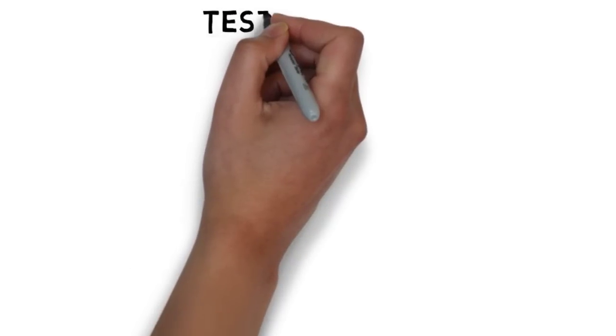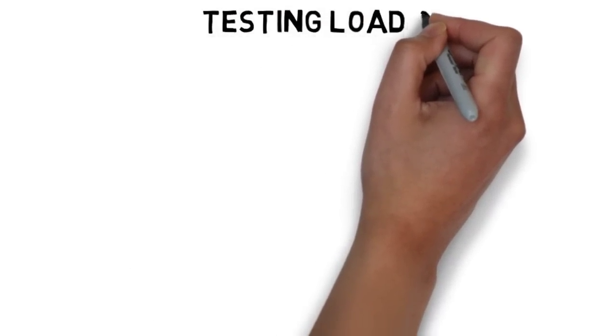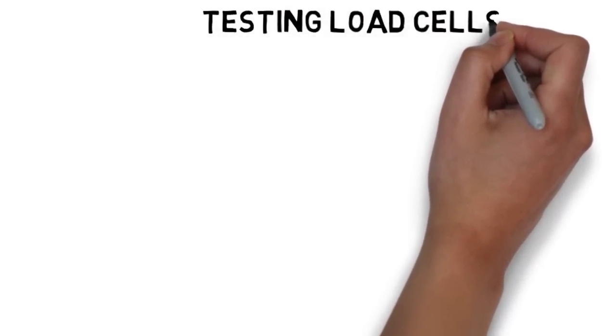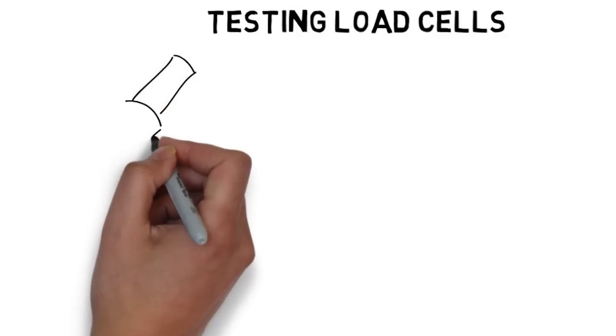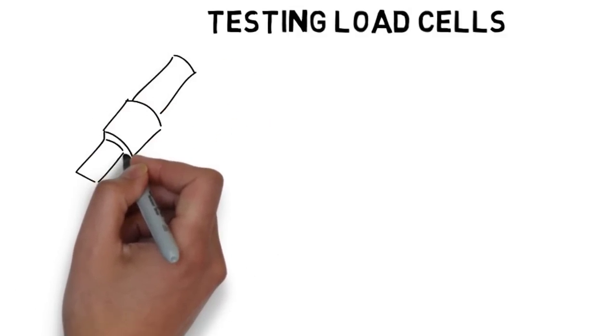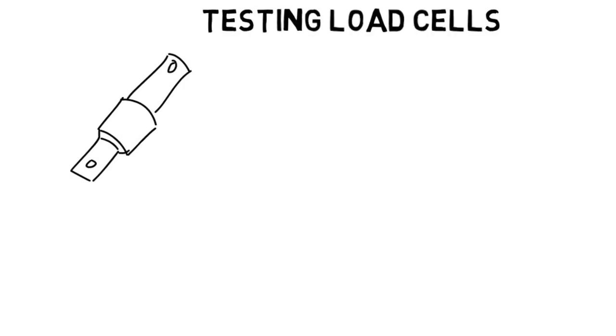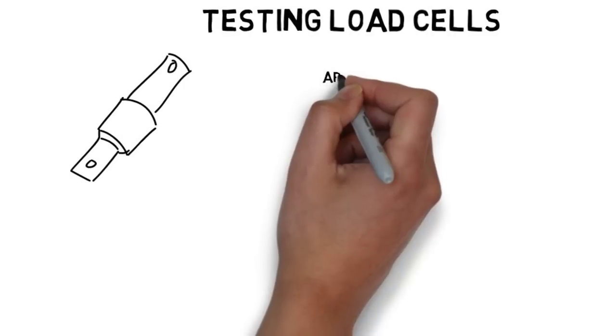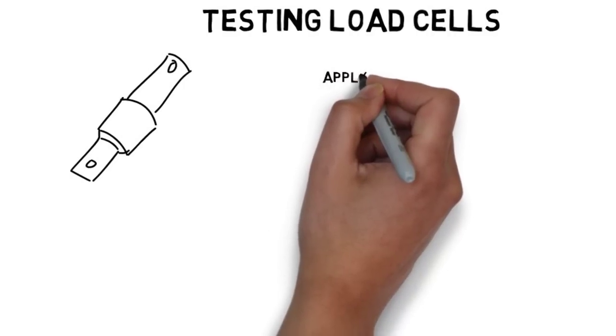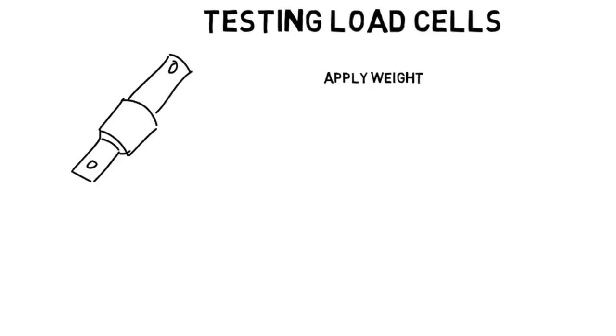The second test you need to do is put weight onto the scale and take the weight off. When you put your weight on the scale, it should weigh roughly your weight times the number of load cells you have. So for a four bar system, if my weight is 200 pounds, it should show roughly 800 pounds.